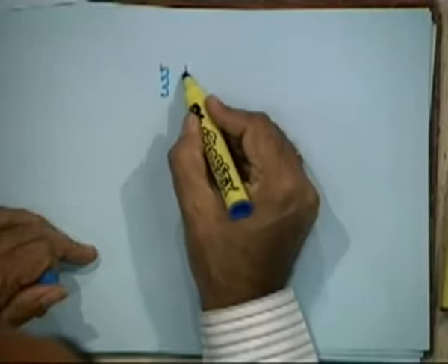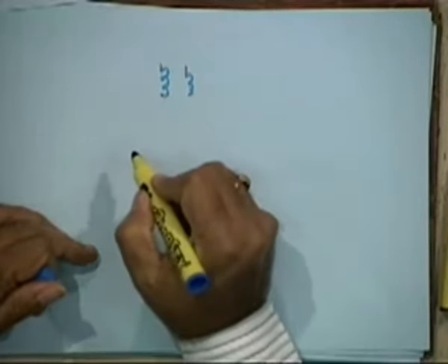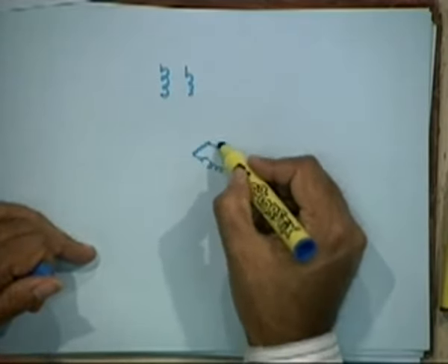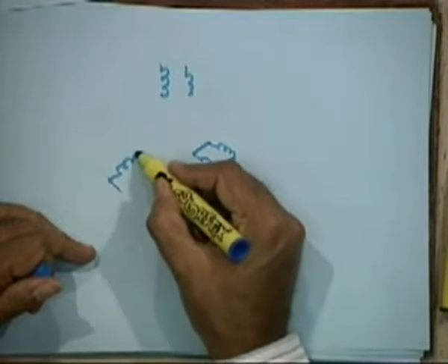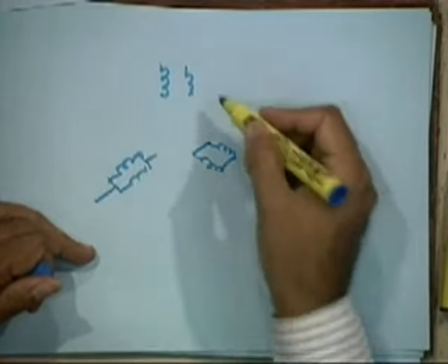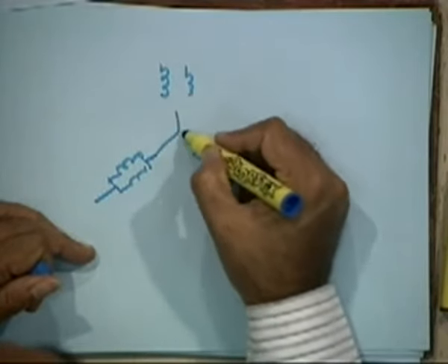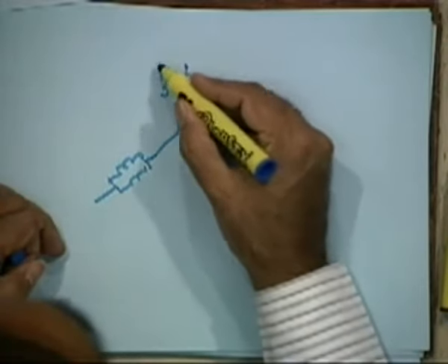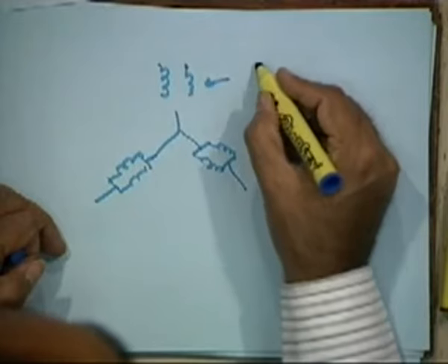Okay. There is also another variant of this part winding starting, as follows. You can have two parallel circuits in each phase, but you do it in one phase only, because you don't disturb the other two phases, so it becomes an unbalanced starting. So you can have in this a series parallel starting.